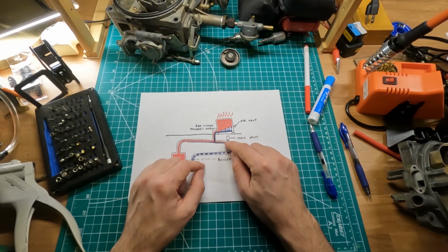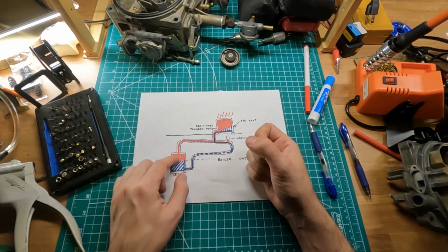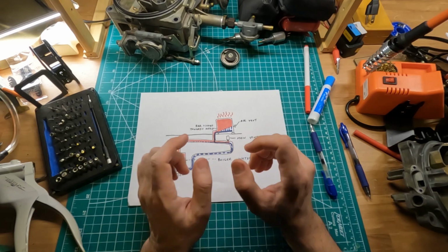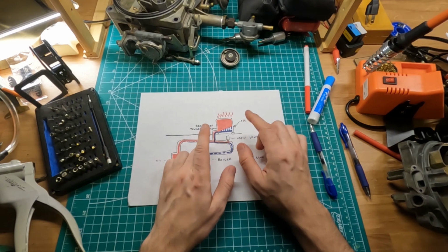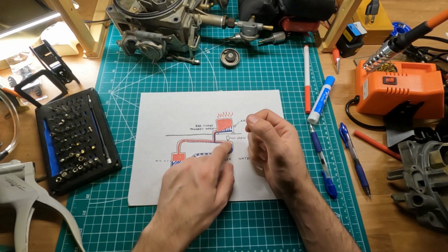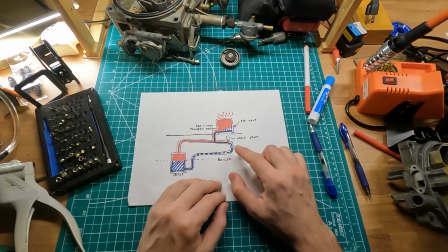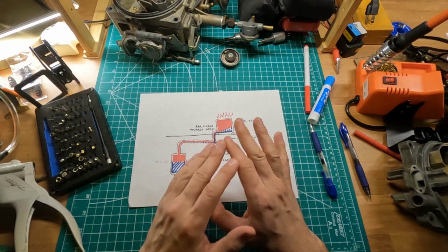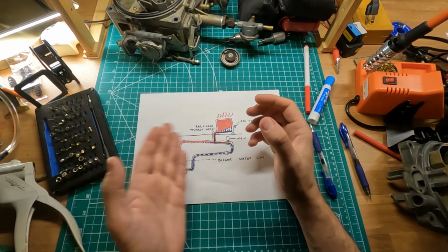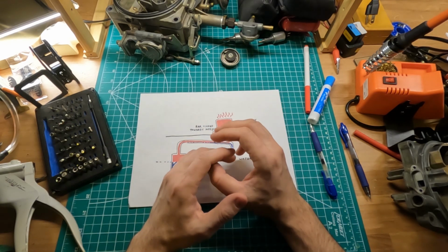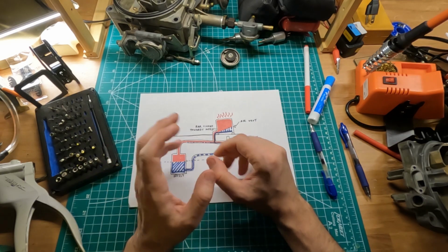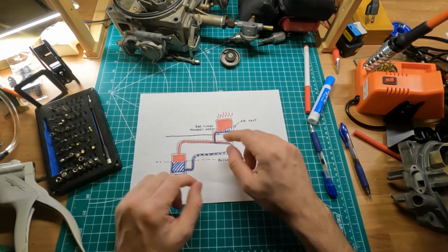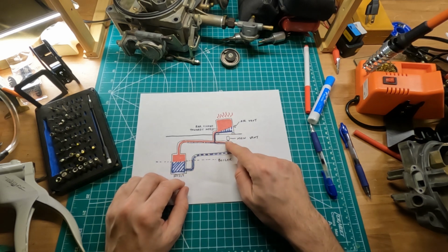And if you kept it as simply an opening, indeed, the steam would push the air all the way outside of the opening. But there would be a problem. Because it's just an opening, the steam would just start escaping via this opening. And because of that, they introduced this thing called a vent. The function of a vent, in its basics, is to allow the air to escape and close itself the moment the steam hits it, so that the steam gets trapped inside here.